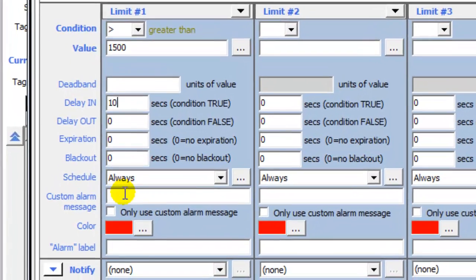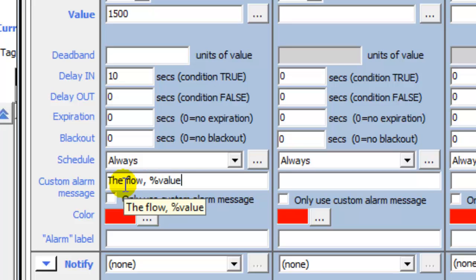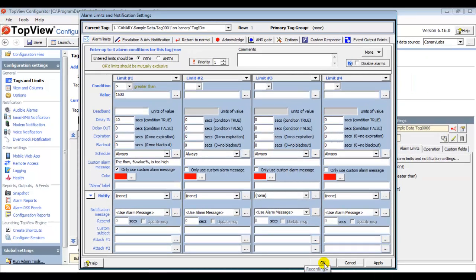I will then enter a custom alarm message: "Flow %Value% is too high," and check the box to only show the custom alarm message. %Value% is a placeholder that will put the current value of the Flow into the alarm message. Because I'm converting the engineering units of this tag by applying an operation, %Value% will be the result of the operation, not the original tag value. I will then click OK to save the current settings and close the alarm limits screen.